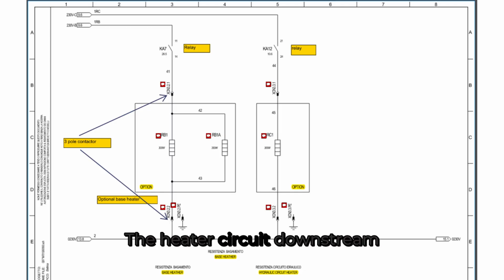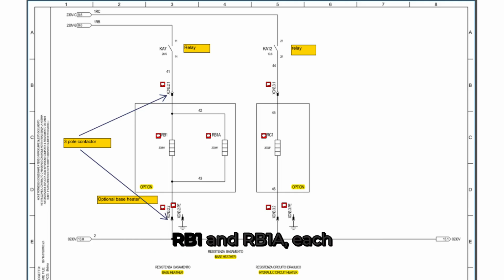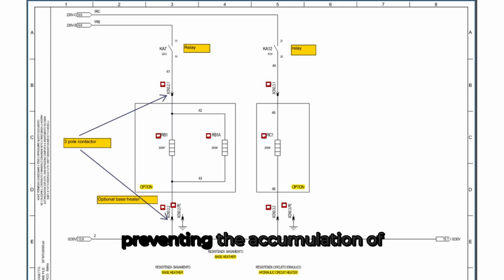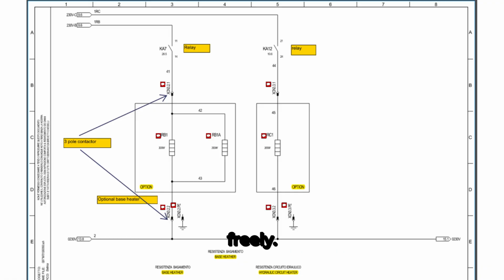The heater circuit downstream of this relay includes 2 base heaters, labeled RB1 and RB1A, each rated at 300 watts. These heaters are connected in parallel to provide even heat distribution across the unit's base pan, preventing the accumulation of ice and ensuring that the condensate can drain freely.